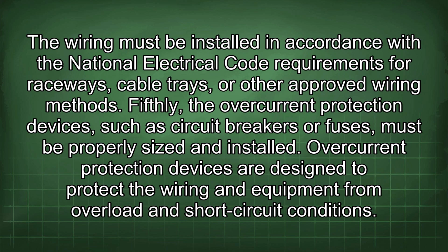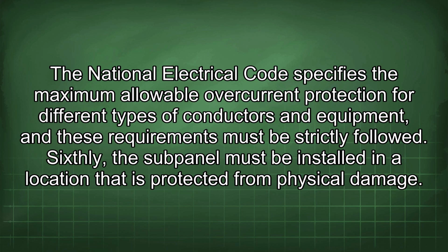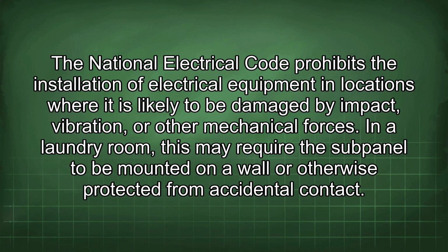Fifthly, the overcurrent protection devices, such as circuit breakers or fuses, must be properly sized and installed. Overcurrent protection devices are designed to protect the wiring and equipment from overload and short-circuit conditions. The National Electrical Code specifies the maximum allowable overcurrent protection for different types of conductors and equipment, and these requirements must be strictly followed. Sixthly, the subpanel must be installed in a location that is protected from physical damage. The National Electrical Code prohibits the installation of electrical equipment in locations where it is likely to be damaged by impact, vibration, or other mechanical forces.